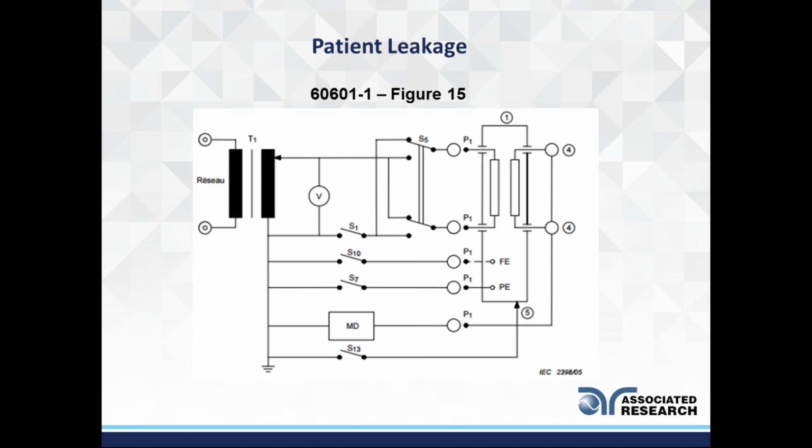I'm lucky to be ignorant that I can't think of parts at a hospital that go on you, because I don't have that experience. But it's some sort of cardiac monitor, right? I want to know how much is leaking from my input power to that heart rate monitor that's going to pass through me and return to ground.